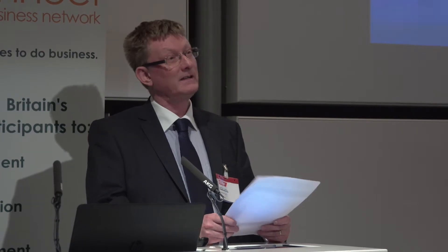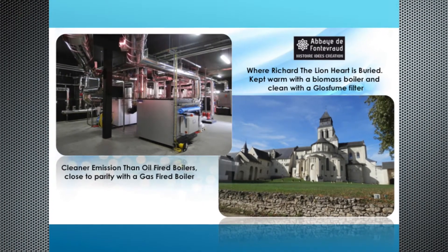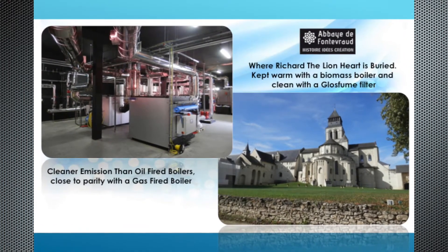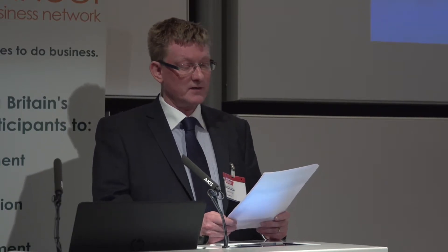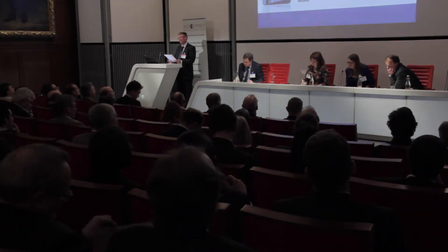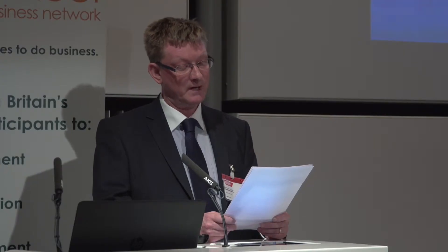Biomass fired boilers are valuable for reducing greenhouse gases, yet they're quite dirty and produce high levels of dust pollution. This pollution contains submicron particulates arising from the fuel ash. The fine particulates are increasingly considered hazardous to health, and regulated limits for emissions are being progressively reduced at the European level. Cyclones have been a popular choice for abatement on these boilers; however, they're inefficient at capturing the small particulates, and the majority of PM 2.5 and below simply passes straight through.